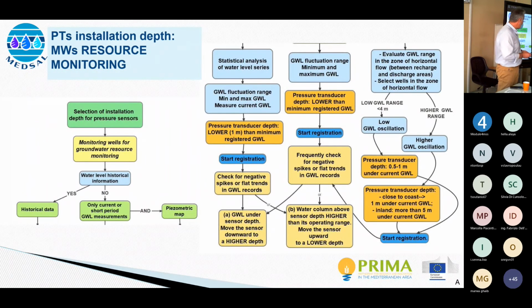In this case, therefore, what you have to check is again the pressure transducer depth that you need to install, taking care of the fluctuation and also of the pressure range. You don't want your pressure transducer to get out of the water column. You don't want your pressure transducer to get deeper than the range it can support. Always keep in mind that pressure transducers come in different operating ranges. You can find pressure transducers that operate from 0 to 1 meter up to 0 to 100 or 150 meters. You select what you want based on the amplitude of the groundwater level evolution in your particular case.